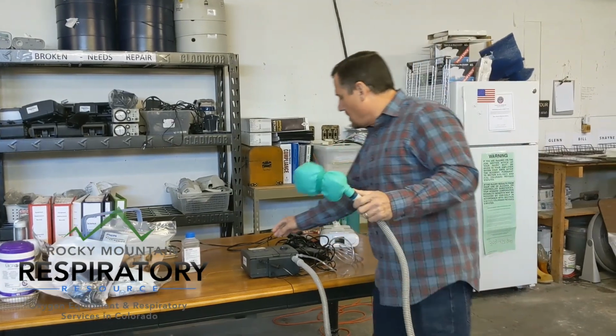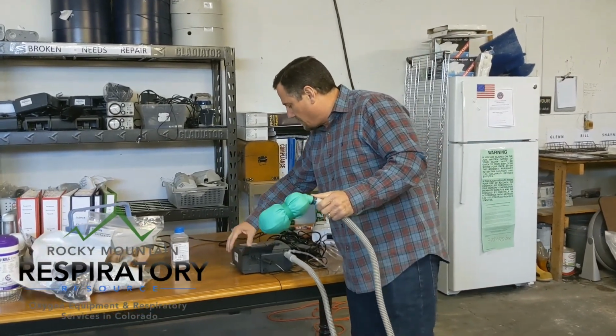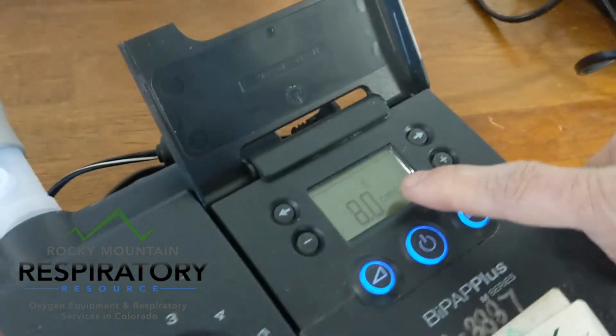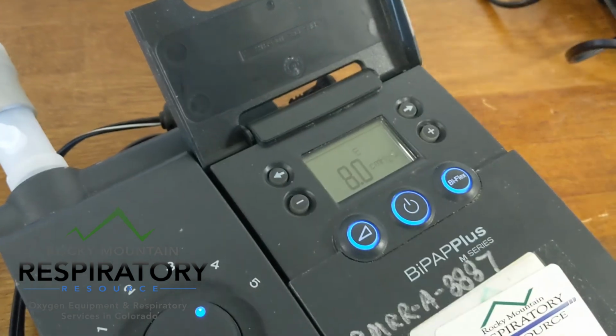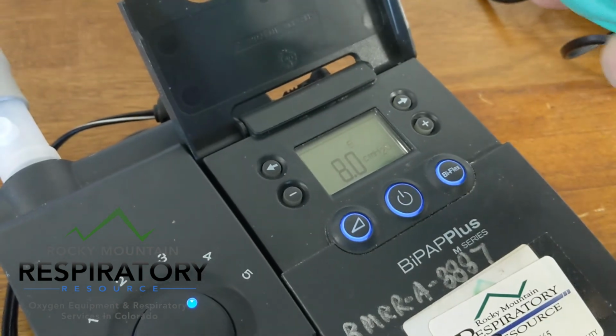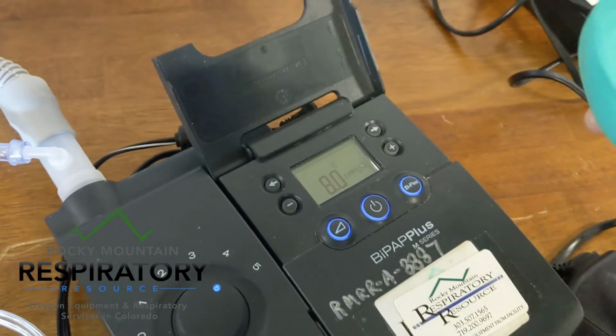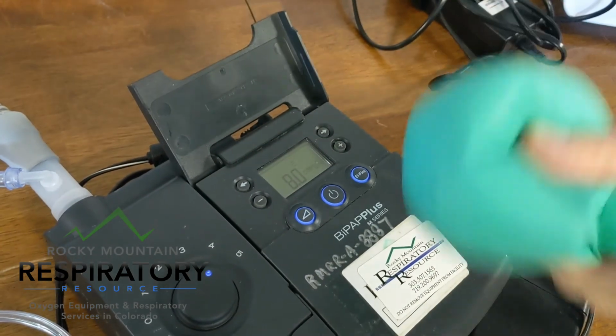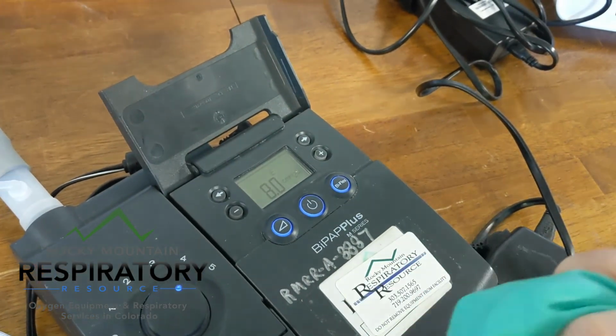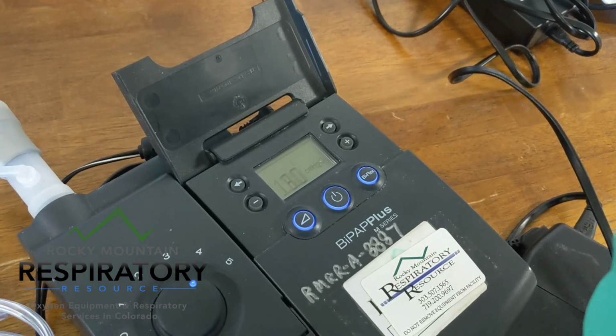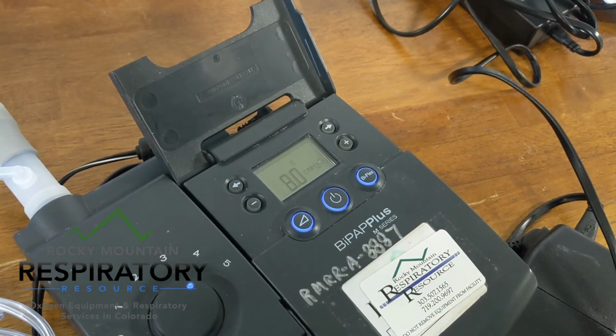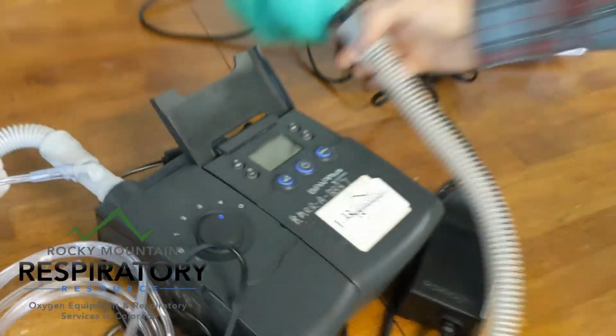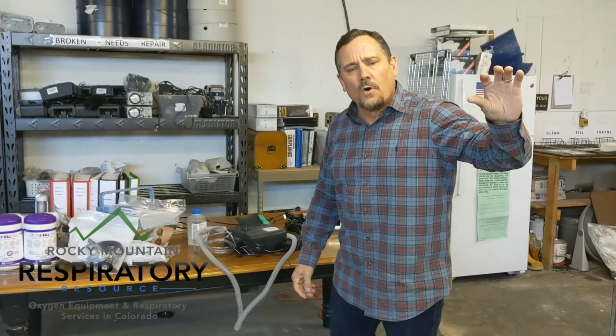Okay? And so what you notice as I look at the screen here to see what the pressure is, this is 8 on the expiratory side. And you can see E, which would be for the EPAP. And as I squeeze the test lung, you can see that it shoots up to 13. So this setting for this BiPAP would be 13 over 8. The IPAP would be 13 centimeters of water, and the EPAP would be 8 centimeters of water.